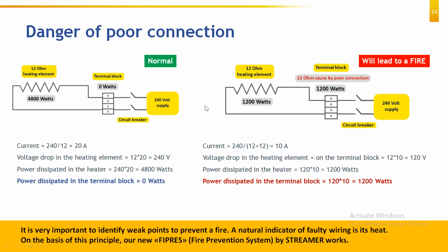So we will continue. Danger of poor connection. This is a particular example which we have taken. In a normal scenario, the 240 volt power supply unit is supposed to supply power, and the circuit breaker and the terminal blocks are supposed to have zero contact resistance. Then we have the heating element, which in this example has around 12 ohms resistance. Because there is no contact resistance on the terminal block or the circuit breaker, 100% of the power supply will come across this heating element.